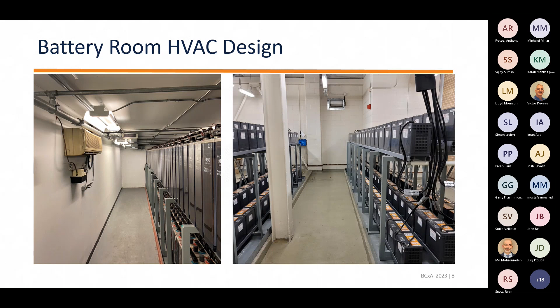Back to climate, you'll see this unit is blowing on the batteries, and that's a big no-no. Not good for the batteries, blowing cold air. Up here you'll see there's an exhaust louver where we found an exhaust fan running around the clock, keeping the room in negative pressure, pushing a lot of air. There's more than one vent here too. These rooms have a lot of ventilation because open lead acid batteries develop hydrogen. Things you got to be careful about, can be quite complicated.